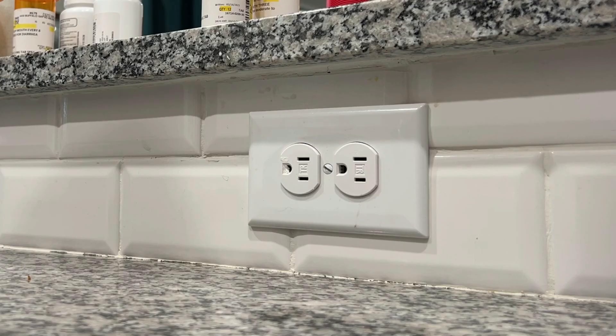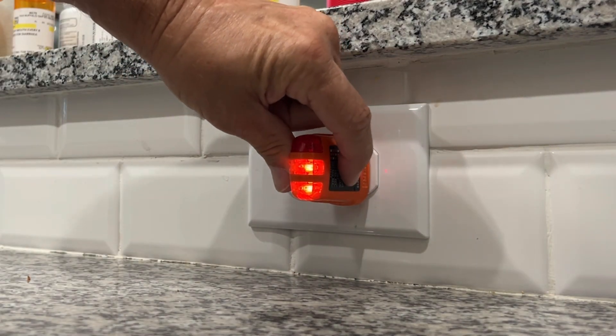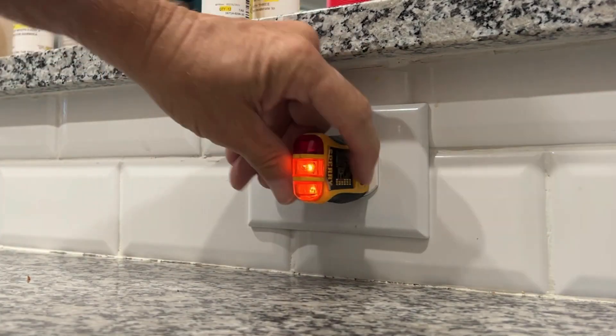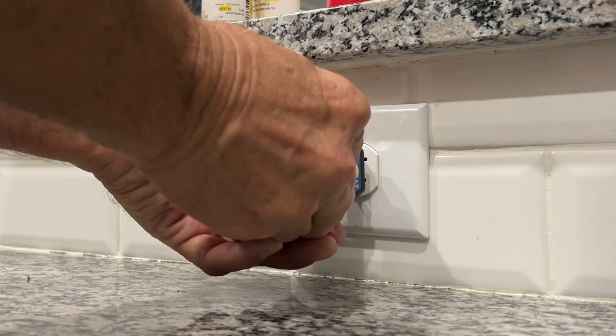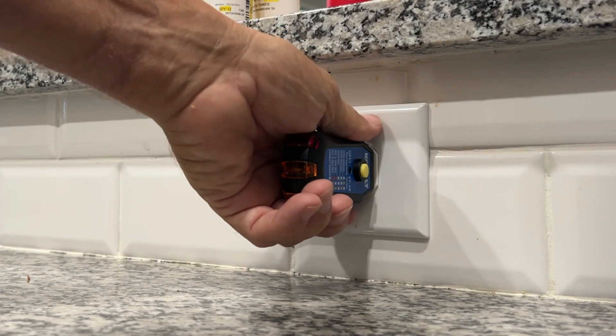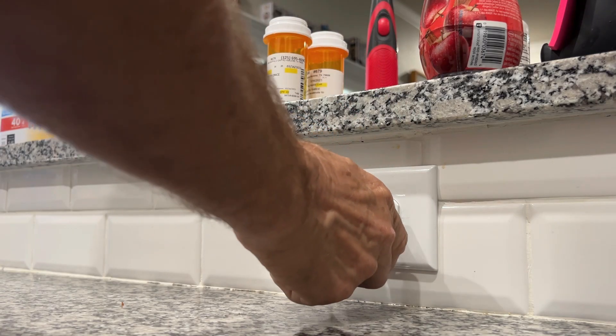The Klein did not trip it. The Sperry doesn't trip it. The Cobalt — it tripped it, and that's very surprising because that was the one I was using during the inspection and it didn't trip it, but this time it did. The green one doesn't trip it either — you can still see the green light.